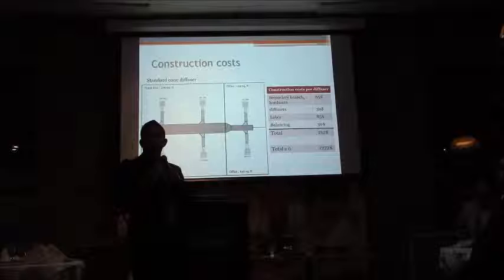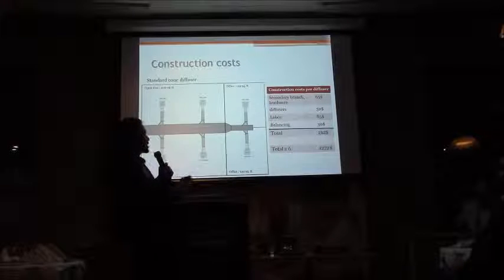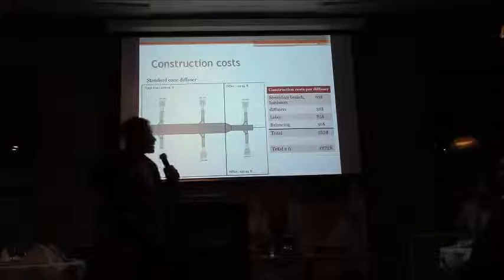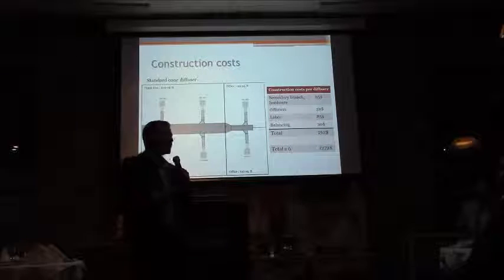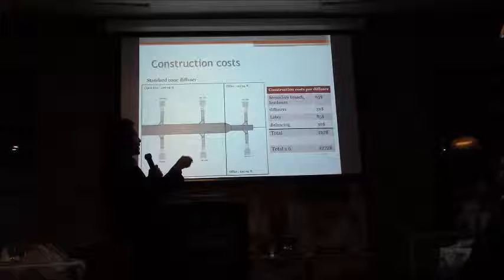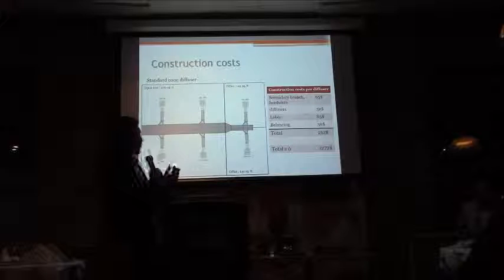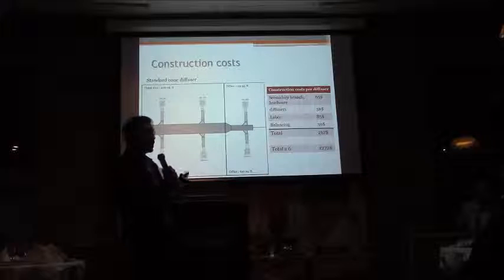Now those are the costs when the same contractors that I asked how much does it cost to treat fresh air, I asked them how much does it cost to install diffusers. And this is the answers that I got. For each secondary branch, it's about $65. That includes your hardware, so there's a damper, there's your duct, and then there's your flexible duct. Each diffuser for a cone diffuser is the most inexpensive diffuser out there, and they're approximately at $32 per diffuser.